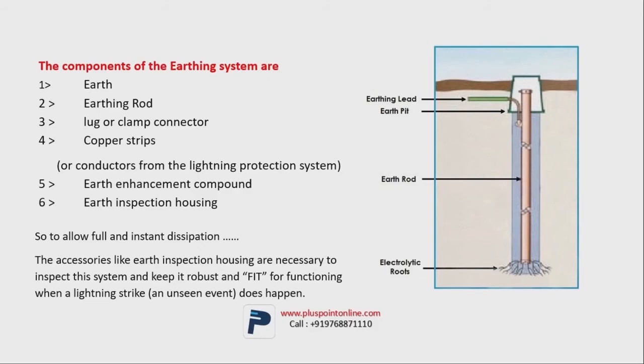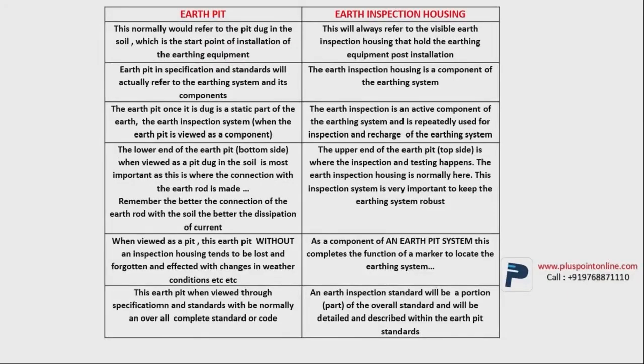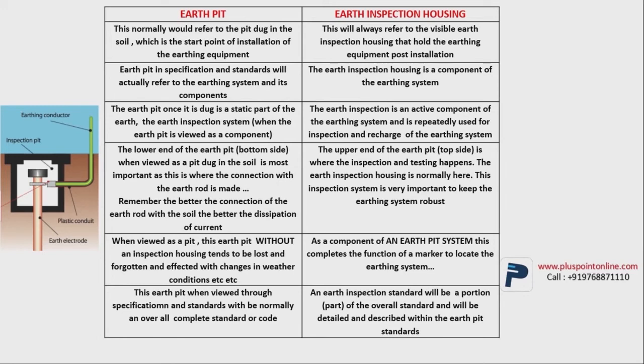Now, let's discuss the difference between the earth pit and earth inspection housing. I'll explain it in simpler words. So the earth pit is regarded as the starting point of the earthing. When you dig a deep hole in the ground, around 10 to 20 meters depending on the requirement to develop earthing, that is called the earth pit. Earth inspection housing is referred to as the ending point of the earthing. Once the earthing is done, the upper part is called the earth inspection housing. According to the IS 3043 standard, the earth pit is made up of a lot of components, whereas earth inspection housing is only one part of the earthing system.